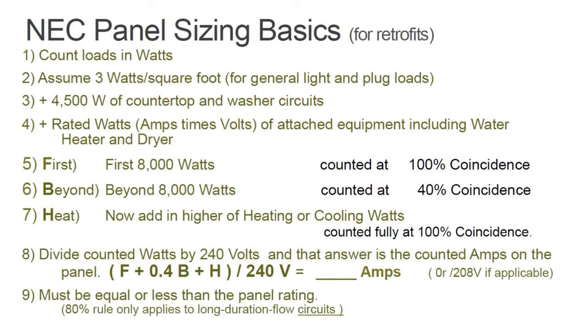But mostly, in what we call the amp diet, I'll be focusing on techniques for choosing equipment, systems, and control strategies that help you get permission to load it all on your existing electric panel. I'll be using a 100 amp panel, a common size here in the Bay Area for smaller panels, while 200 amp panels are the other common size for new construction. An ampere is a measure of current flow, and a 100 amp panel lets 100 amps flow through it at 240 volts.